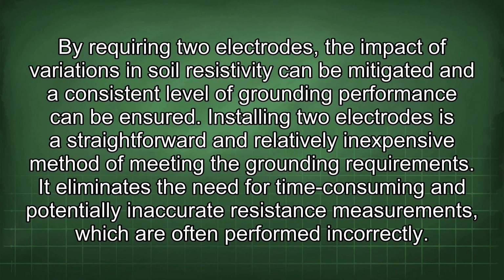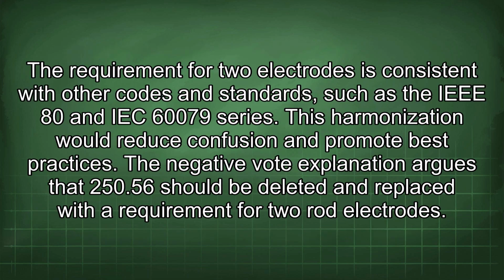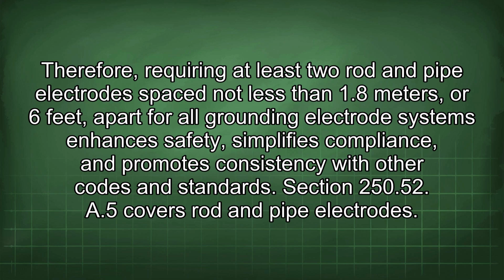It eliminates the need for time-consuming and potentially inaccurate resistance measurements, which are often performed incorrectly. The requirement for 2 electrodes is consistent with other codes and standards, such as the IEEE 80 and IEC 60079 series. This harmonization would reduce confusion and promote best practices. The negative vote explanation argues that 250.56 should be deleted and replaced with the requirement for 2 rod electrodes. Therefore, requiring at least 2 rod and pipe electrodes spaced not less than 1.8 meters or 6 feet apart for all grounding electrode systems enhances safety, simplifies compliance, and promotes consistency with other codes and standards.